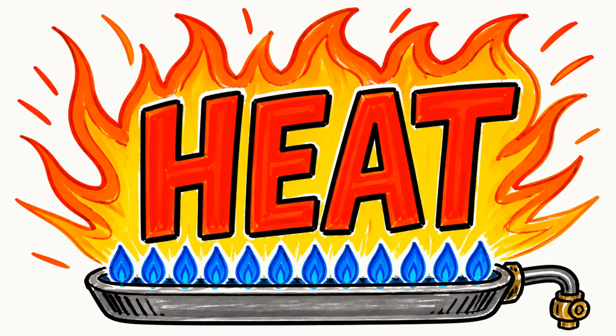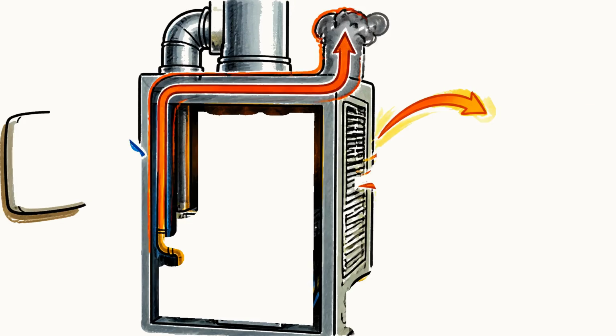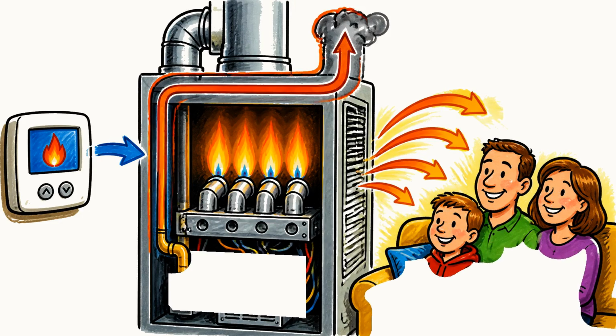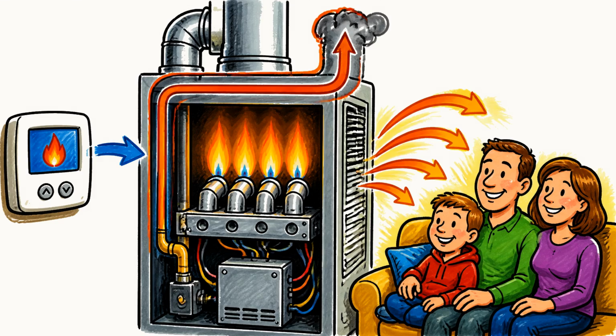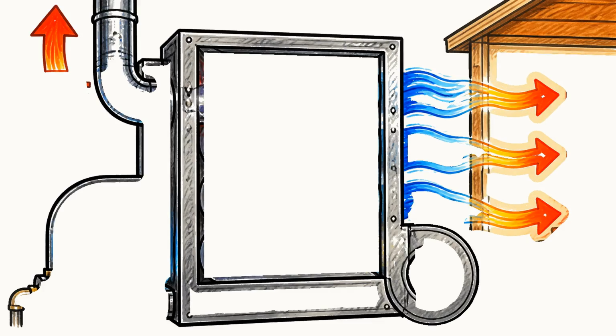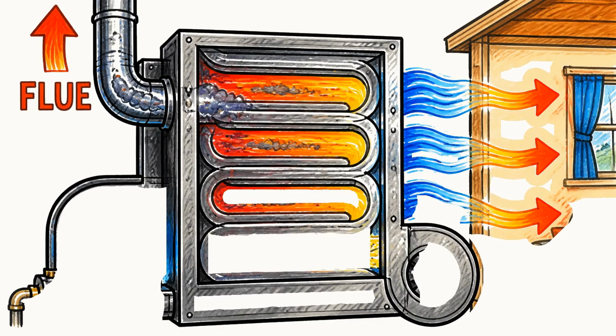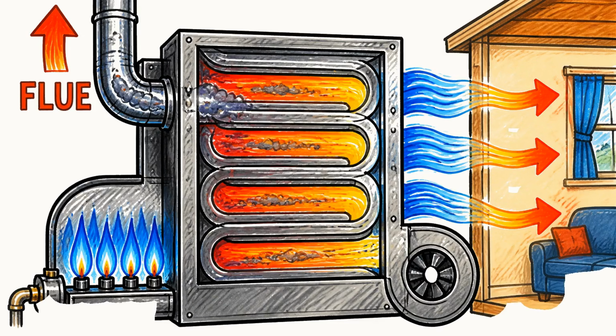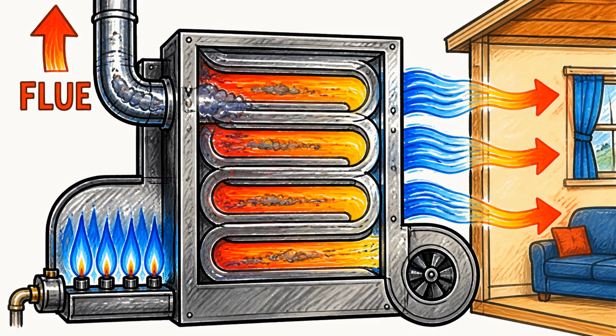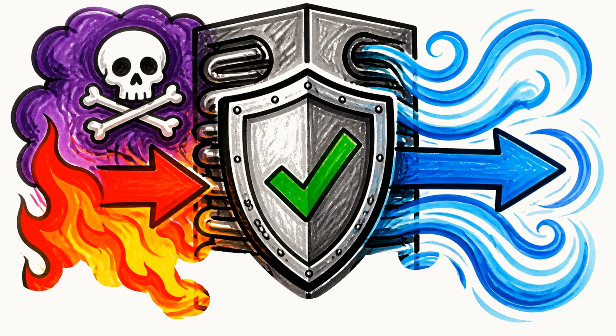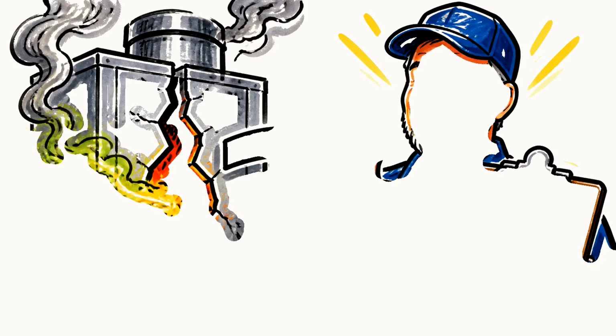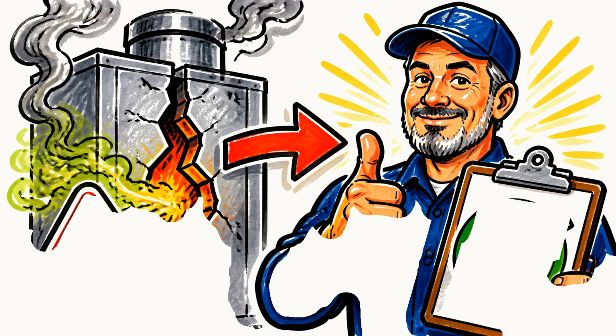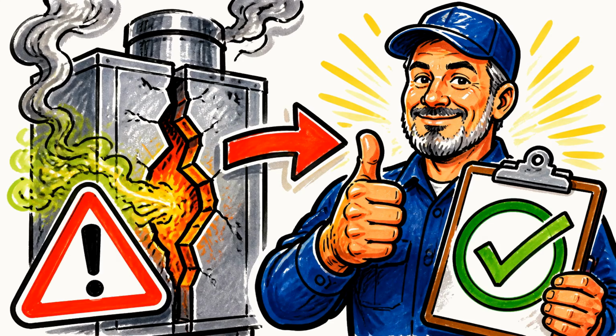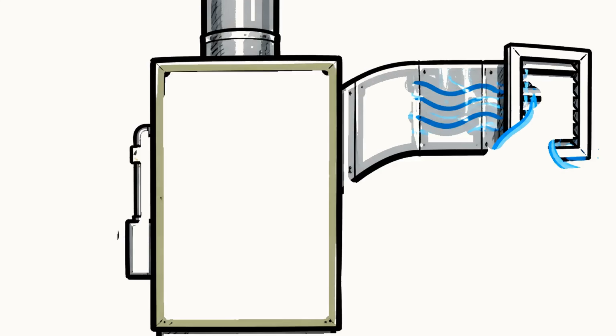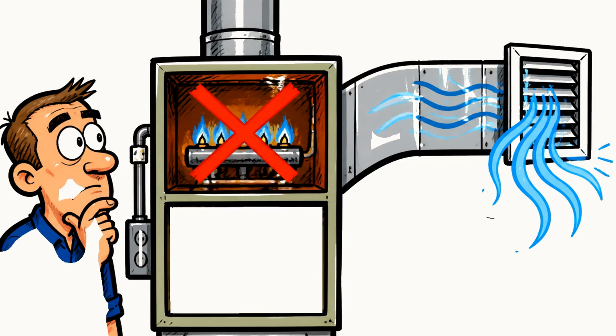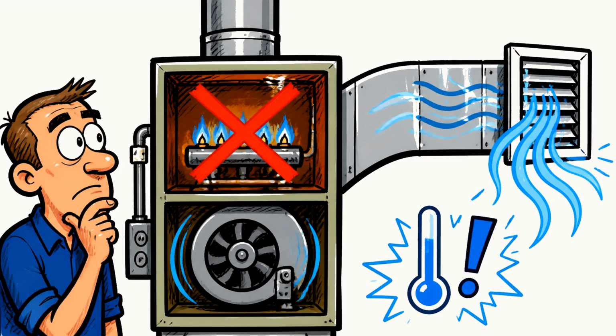Now, onto the heat itself. When the thermostat calls for warmth, a gas furnace lights its burners and makes a real flame, but that fire and its exhaust never touch the air you breathe. They run through a sealed metal part called the heat exchanger, and your house air blows over the outside of it and picks up the warmth, while the fumes, carbon monoxide included, get carried out the flue. That separation is the whole safety story of a furnace. It is also why a cracked heat exchanger is a serious problem, and why a once-a-year furnace checkup earns its price on that one crack alone. If your furnace runs the fan but blows cool air, the heat side never lit or shut itself down, which is a different problem than getting no air at all.